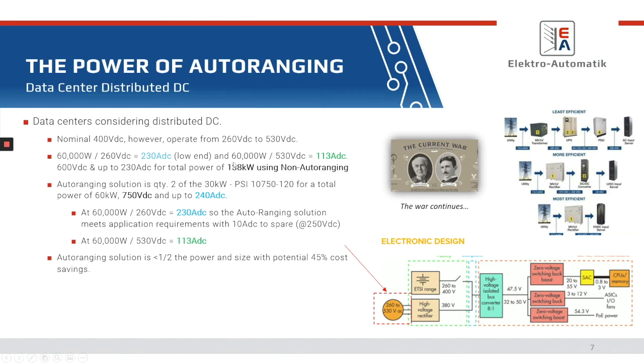Okay, so let's take a look at auto ranging power supplies. Again, we take that 60 kilowatts. What we decided to do is say, hey, let's take two 30s and put them in parallel. You'll notice you're getting that 750 volts, well beyond the 530 volts required. So there's plenty of headroom for planning for the future. It provides up to two units in parallel, up to 240 amps DC. So 60 kilowatts, 260 volts, you get your 230 amps within the capability. And again, certainly the voltage is within capability, 113, you're good to go. So again, in this particular example, the auto ranging solution is about half the power and results in about a 45% cost savings over a standard power supply.